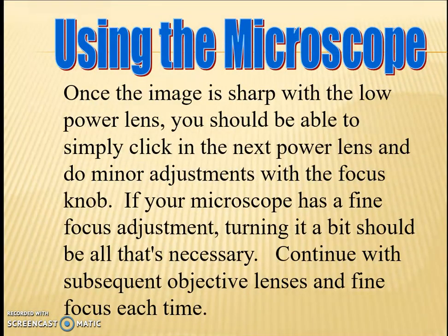Once the image is sharp with the low power lens, you should be able to simply click in the next power lens, which is going to be 10x, and make minor adjustments with the focus knob. If your microscope has a fine focus adjustment, turning it a bit should be all that's necessary. Continue with each subsequent objective lens and fine-focus each time.